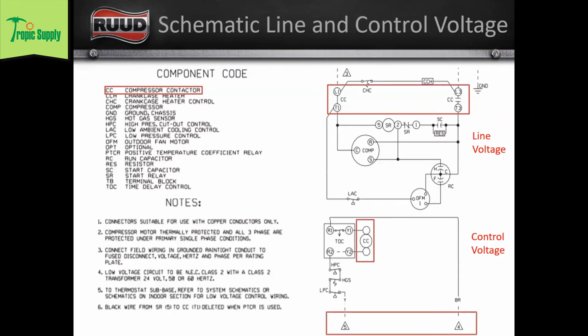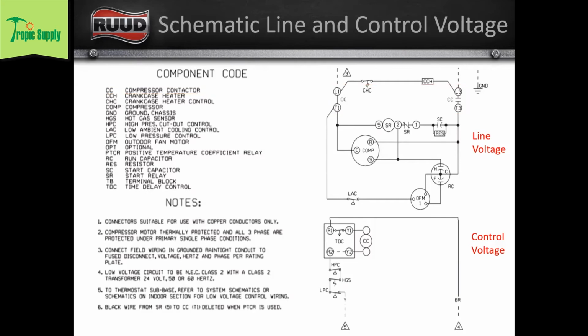Wade, we have a question back on the low ambient control and the crankcase heater. If the low ambient control opens on a temperature drop, why is the symbol not the same as on the crankcase heater control? The symbol looks like a pressure control.